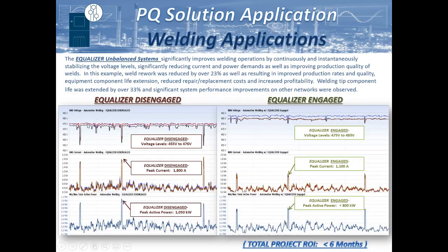So you can see here with the system disengaged that we're having these large voltage sags on these two phases, with a peak current of about 1800 amps. Whereas once we engage the system, we raise that voltage level and minimize this voltage sag to about 2 or 3 volts. This has a resulting effect on the peak currents. So once again, you can see that by reducing these peak currents by about 700 amps, this has a significant impact on extending the life of the welding tips. It actually increases the quality of the welds. In this particular case, it reduced their rework requirements on welds by over 23%, and extended the life of the welding tips by 33%. So real big impact.